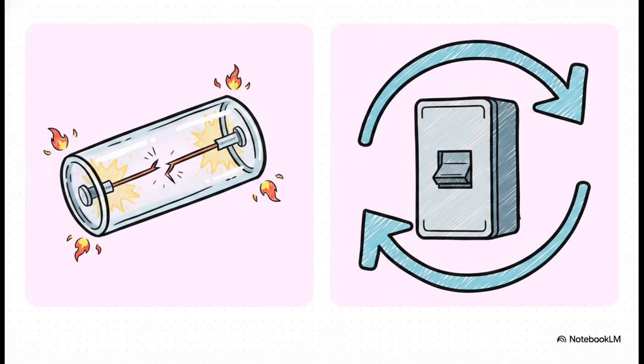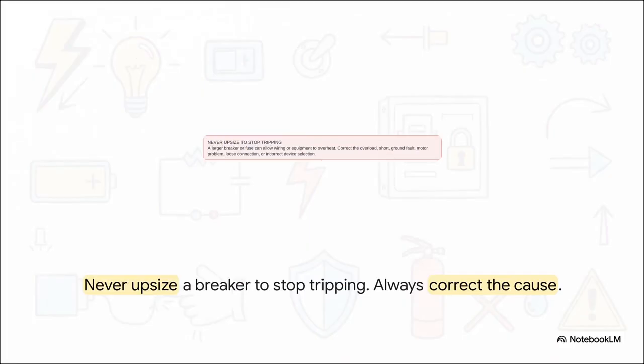A circuit breaker, on the other hand, is a resettable overcurrent device. When it detects an overload or a short circuit, an internal mechanism trips, throwing the handle to a middle position and opening the contacts. Both do the exact same vital job, protecting your conductors and equipment from destructive overcurrent. And this leads us to the absolute golden rule of electrical maintenance. Always correct the cause, never upsize a breaker to stop tripping.